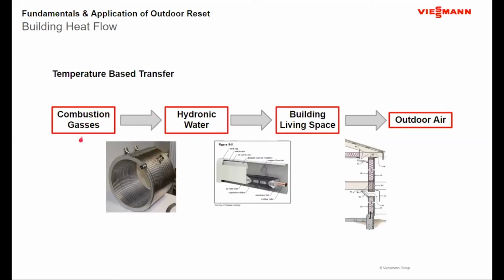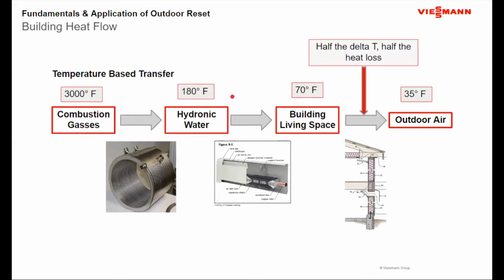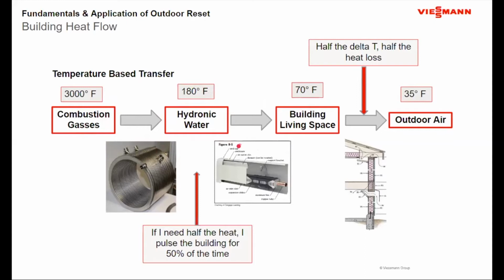What I mean when I talk about pulsing the building is I don't change anything. My living space stays the same. My boiler water temperature stays the same. So when the outside temperature changes and this number changes, how I'm going to affect the process is, instead of running continuously on the flow through the heat emitter, I'm going to periodically turn the pump on or open a control valve, apply water to my heat emitter, pulse the building with heat, if you will, until the thermostat controlling the temperature is satisfied. At that point, I stop that pulse of heat. So I turn the pump off or shut a control valve. My heat emitter stops releasing heat until the thermostat drifts down through its differential and says, okay, it's time again.